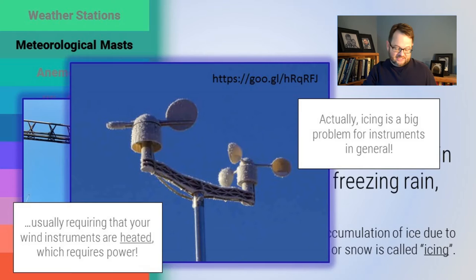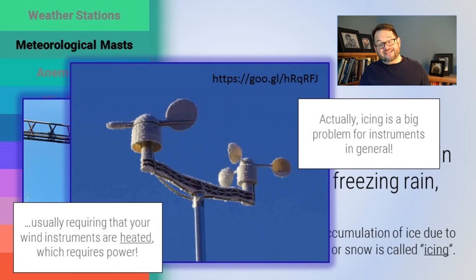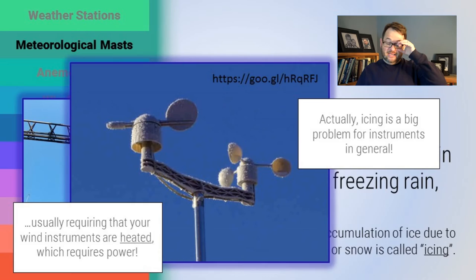Icing is a general problem in meteorology when it comes to instruments. When there's freezing rain or freezing fog, instruments get crusted with ice, which greatly influences their performance. Even if the instrument is still sending data, there's no reason to think it's sending correct information — do we really think a cup anemometer covered with ice is accurately reporting wind speed? This usually requires that instruments be heated. Most wind vanes and anemometers, especially at unmanned stations or up on masts, need procedures to ensure they are not accumulating ice.